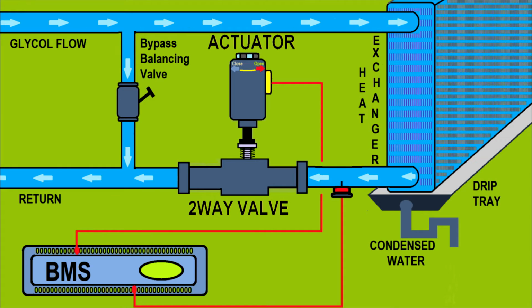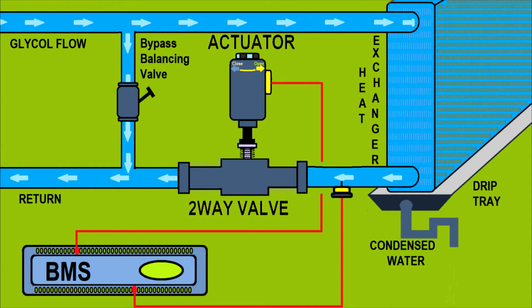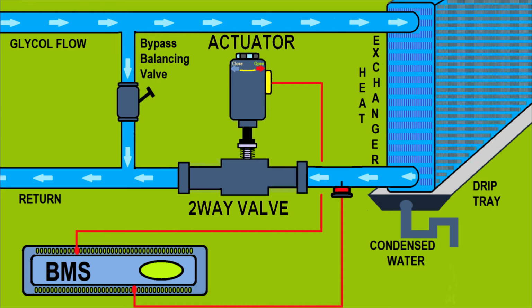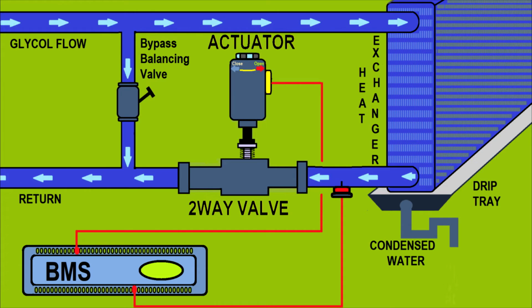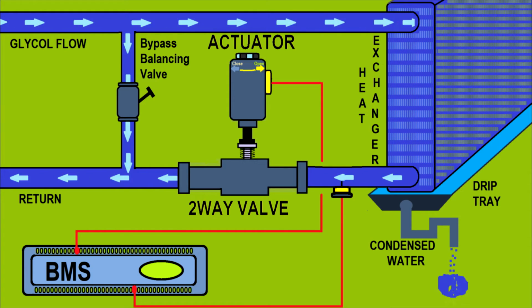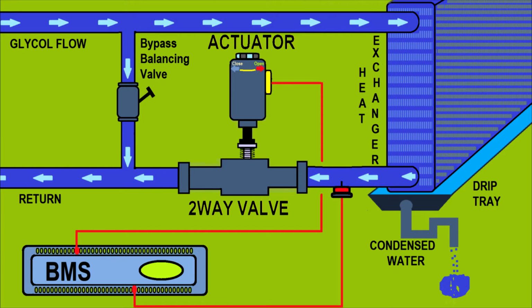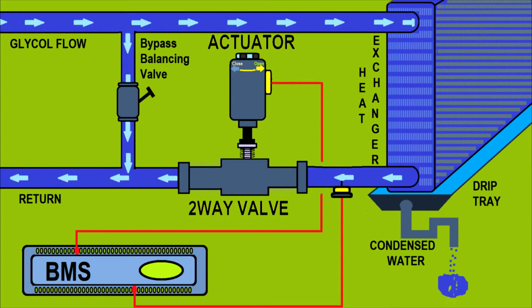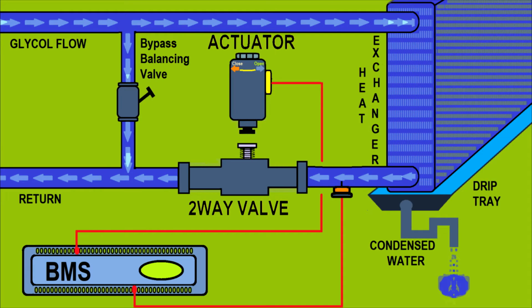You'll see the condensed water, the drip tray, the condensed water pipe, and now you run this system above the dew point. Do you see? You're not removing any moisture from the air because the condensate water pipe doesn't show any water, and the drip tray is empty. If you run this unit a little bit cooler, you see now the water will condense on the heat exchanger, and on the condensed water drain you will see water, which means you're dehumidifying the air.